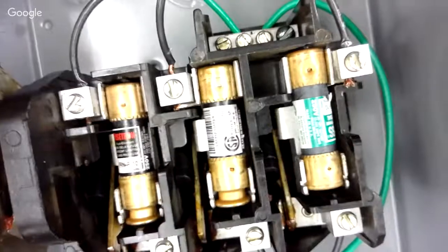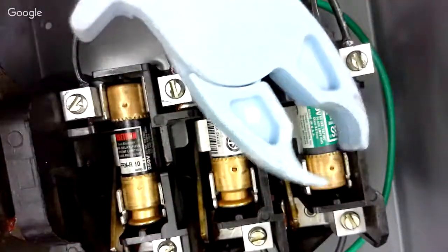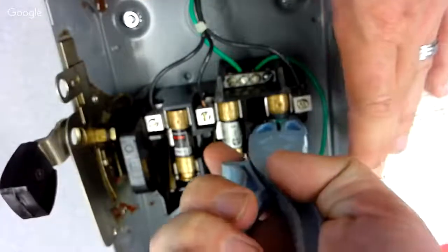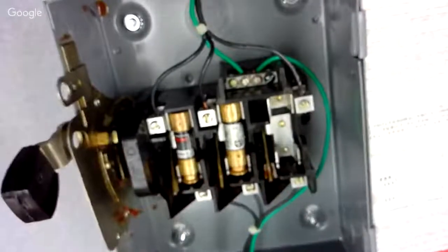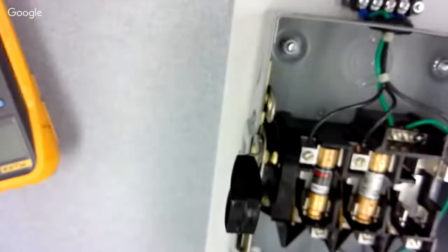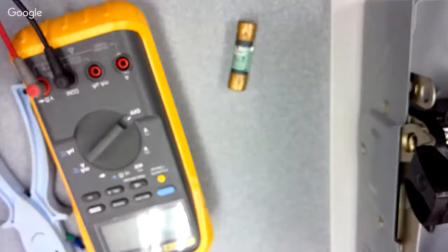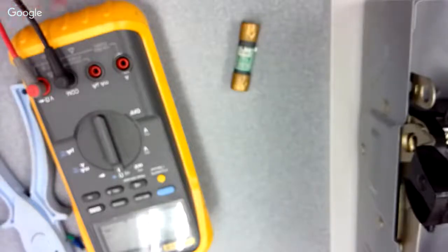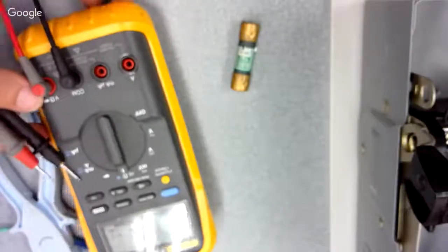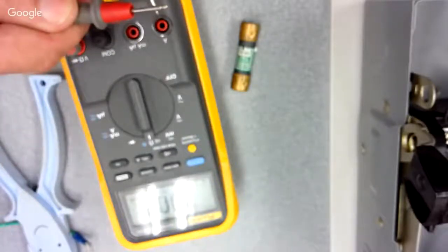Cut this part out. All right, so we're going to take our fuse puller. Notice it is plastic. We're going to come in here and we're going to pull this fuse out. Grab it. This should be bolted, but I'm going to have to hold it down and pull straight out. It should come right out. Now we're going to come over here. We've got our fuse. We're going to turn our meter to ohms. First thing we're going to do is check our meter to make sure that it is functioning. And yes, it is. We're going to take the leads.